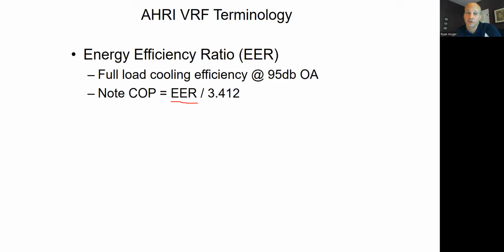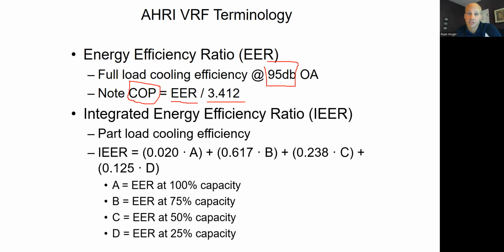And if you ever want to convert from EER to COP for any product, you divide it by 3.412. But just remember, it's that COP at whatever instance in time that it was rated, in this case, 95 degrees with all the zones maximum calling. We have IEER, Integrated Energy Efficiency Ratio. This is my part load.